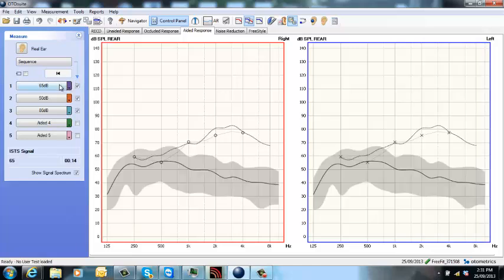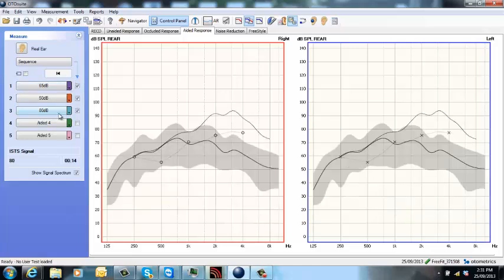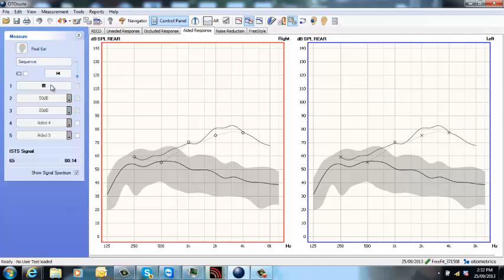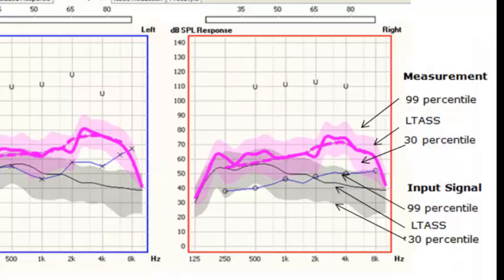Now when I hover over each of these buttons, you can see that I get different responses. Let's look at the first one. The dotted line in the middle, that will be your target response. The solid line represents the signal spectrum, which is the static average for the input signal. The shaded area represents the percentile curves, and this is a dynamic view of the signal spectrum measured at the eardrum.